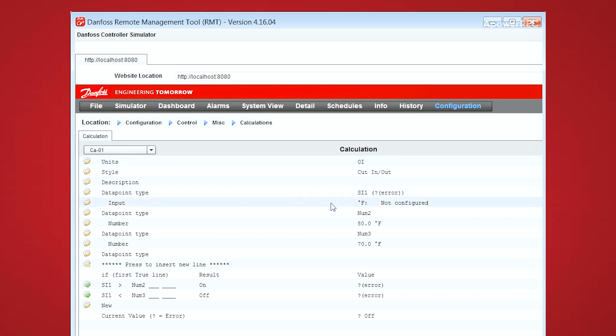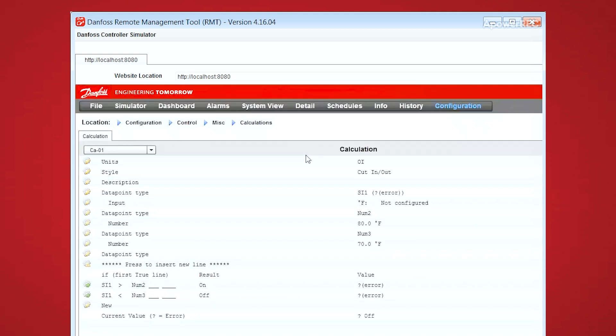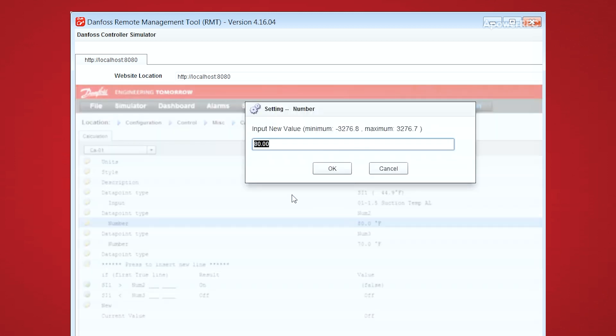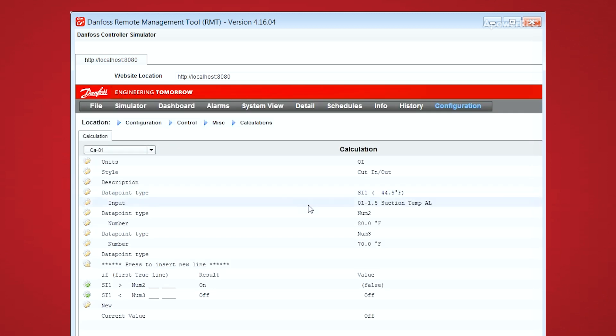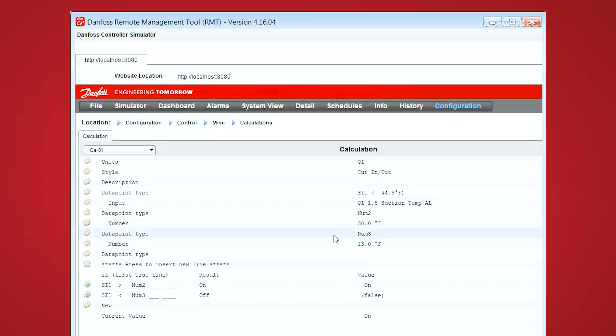In our case, let's have a look at the suction temperature, and we would compare that to two particular values. So if the suction temperature was over 30 degrees or below 15 degrees, then this calculation would become true.